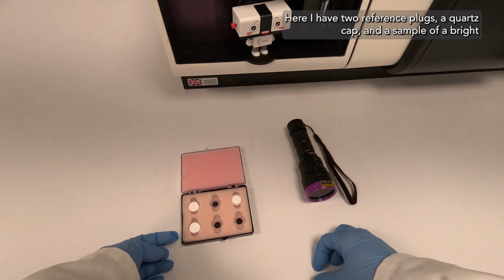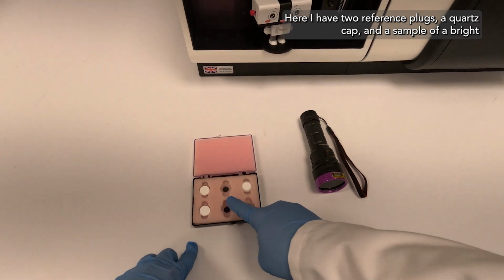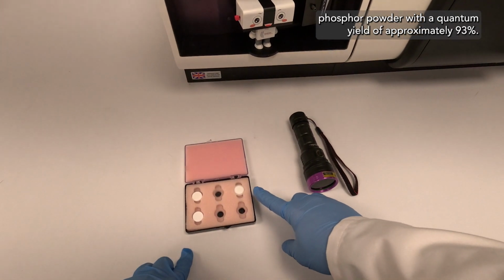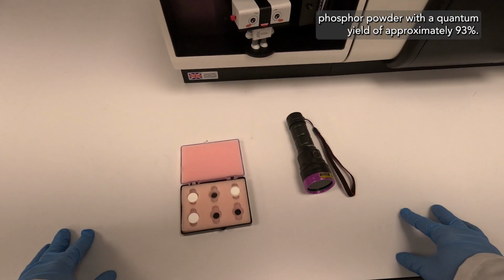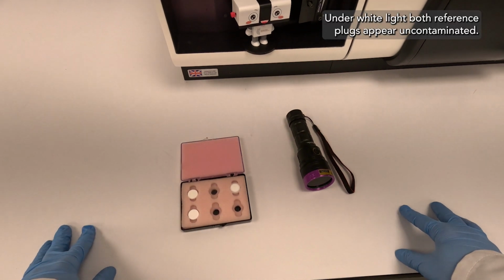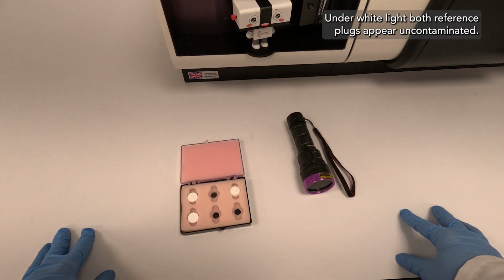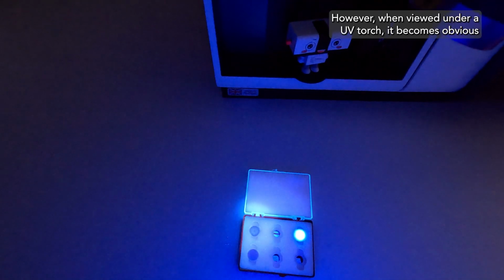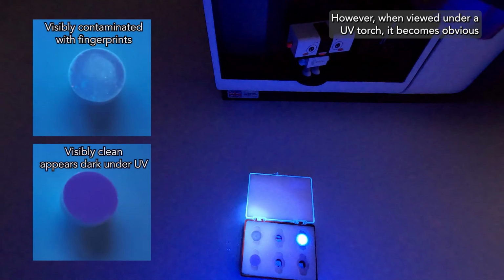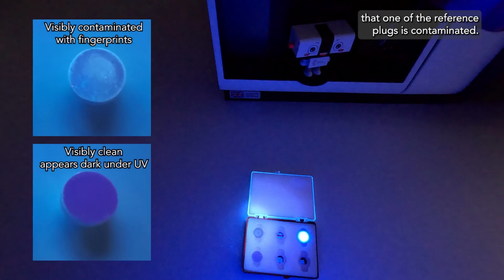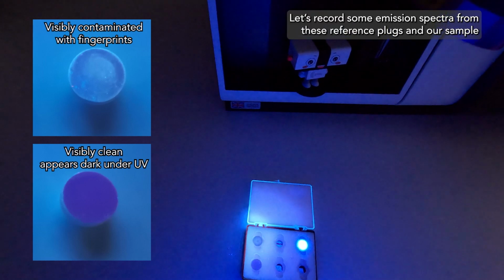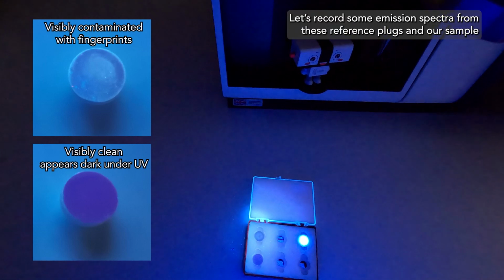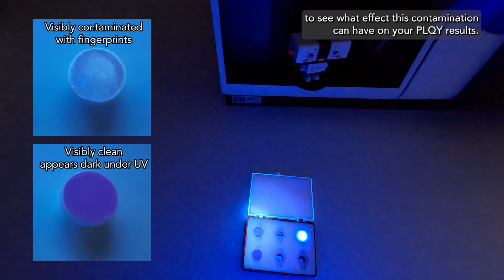Here I have two reference plugs, a quartz cap, and a sample of a bright phosphor powder with a quantum yield of approximately 93%. Under white light, both reference plugs appear uncontaminated. However, when viewed under a UV torch, it becomes obvious that one of the reference plugs is contaminated.